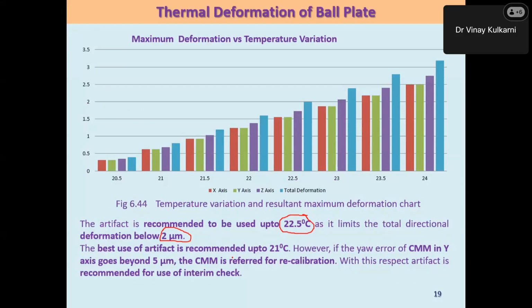The best use of the artifact is recommended up to 21 degrees centigrade here. However, if the yaw error of the CMM in the Y-axis goes beyond 5 microns, the CMM is referred for recalibration. So we can use it up to 22.5 degrees centigrade temperature here in India.